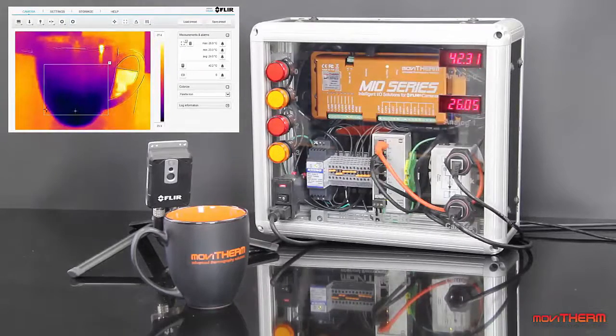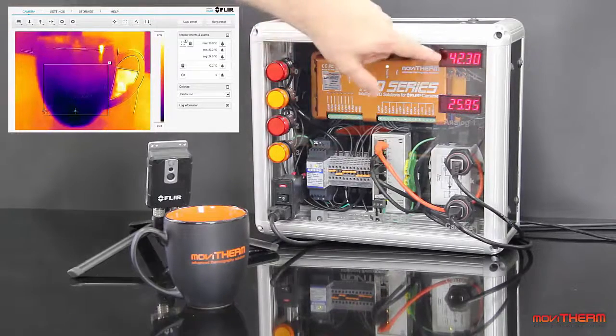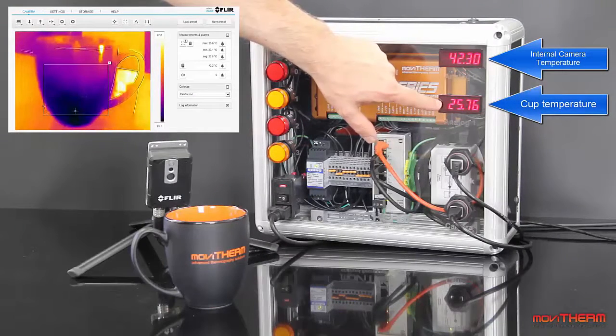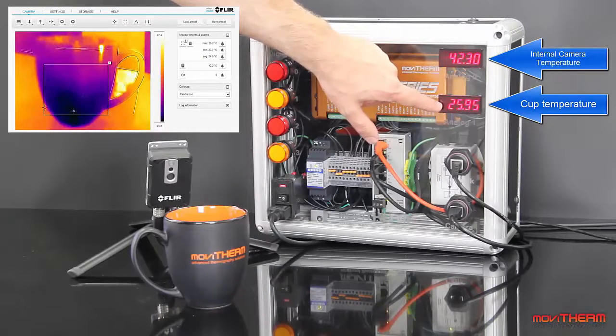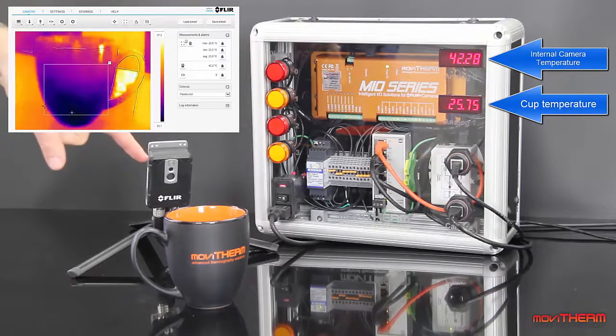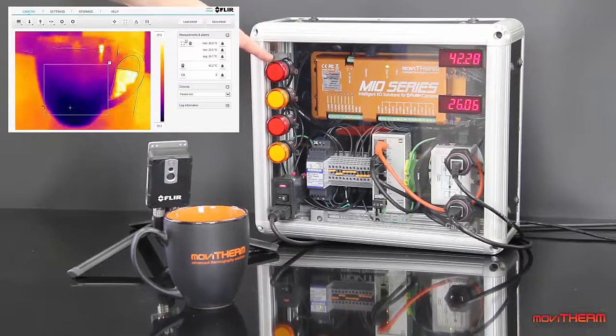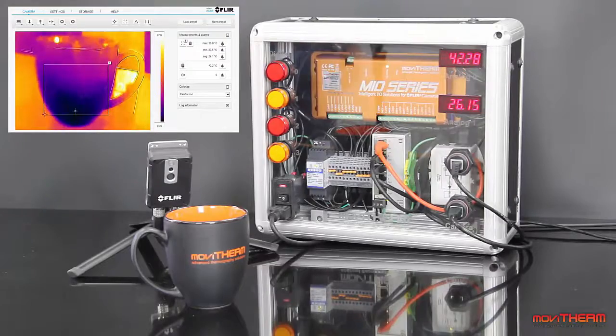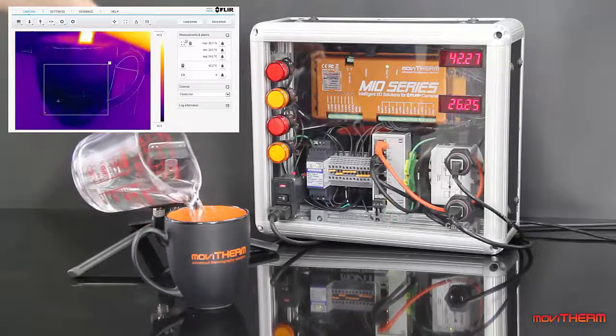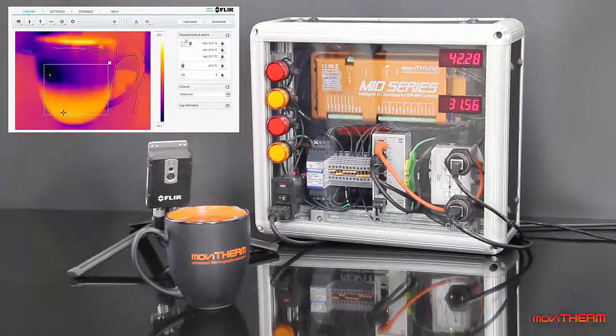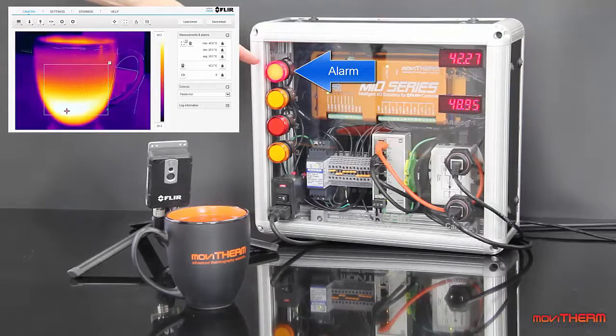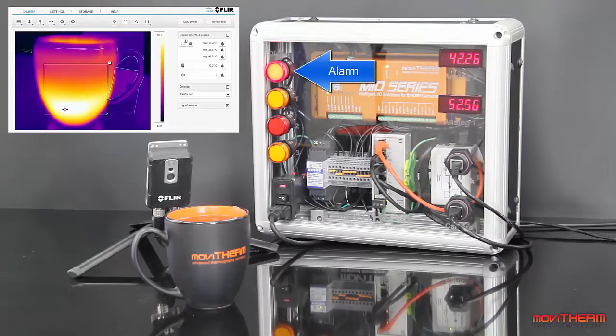Now we can go back to the live camera image and see if we can trigger the alarm. We have set up a monitoring region in the camera and configured the upper analog indicator to display the internal camera temperature. The lower analog indicator shows the maximum temperature in the region we defined — in this case, the temperature of the cup. We are going to pour some hot water into this cup and watch what happens to the indicators on the demo panel. Keep in mind we have set the alarm to 45 degrees C. As you can see, the temperature in the lower indicator is climbing as the cup heats up — and there's the alarm when the temperature goes above 45 degrees C. That's all you need to do to set up a Mio monitoring system.